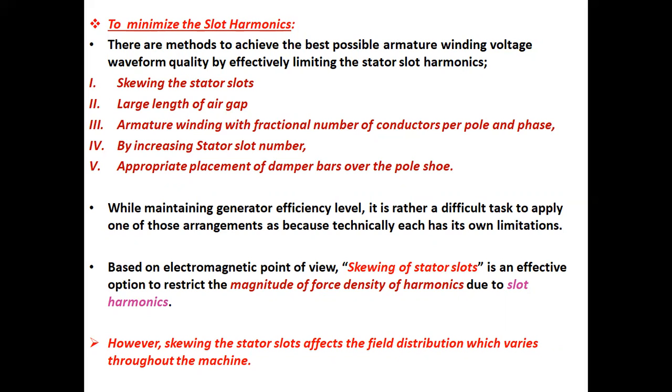While maintaining generator efficiency level, it is rather a difficult task to apply one of those arrangements, because technically each has its own limitations. From an electromagnetic point of view, skewing of stator slots is an effective option to restrict the magnitude of force density of harmonics due to slot harmonics. However, skewing the stator slots affects the field distribution, which varies throughout the machine.